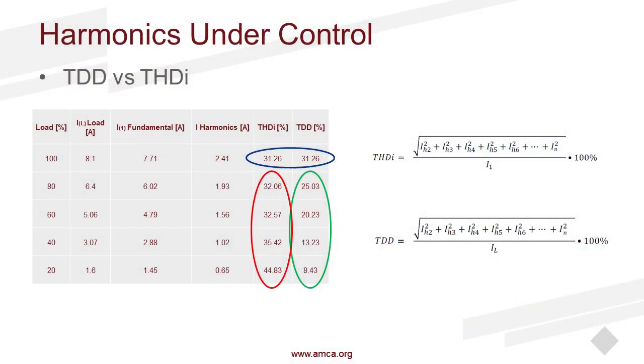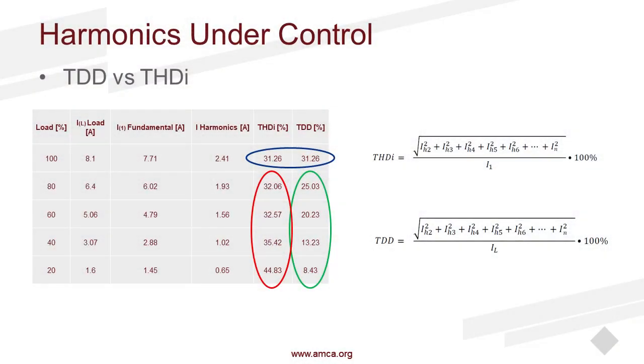So for the red, you're saying, okay, 0.65 harmonic amps is with the ratio of your fundamental current. So this is your 1.45. This is why you're seeing an almost 45% THDI. If we look at the 8.43, then we're seeing the ratio of our full fundamental harmonics, which is 7.71 to the 0.65. So this is why you're seeing that ratio difference. And this is why it's important with IEEE 519. It's not talking about a single device or component or part of your system. It's looking at the total system.